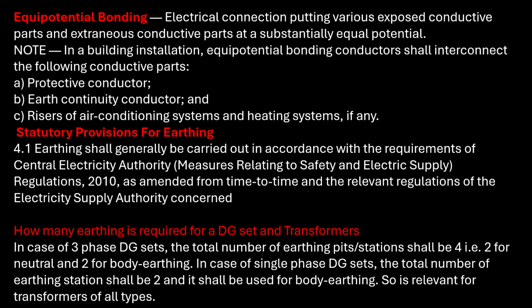Earthing shall generally be carried out in accordance with the requirement of Central Electricity Authority measures relating to safety and electrical supply, Regulation 2010, having amendment from time to time, and relevant regulation of the electrical supply authority concerned. How many earthing is required for DG set and transformer? In case of three-phase DG sets or transformer, the total number of earthing pit stations shall be 4, that is 2 for neutral earthing and 2 for body earthing.